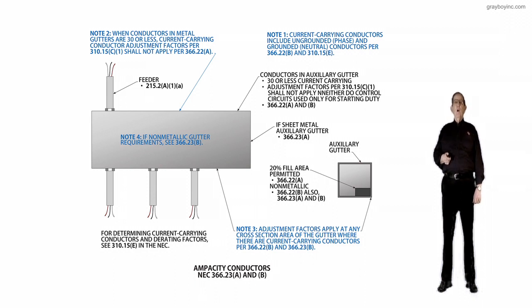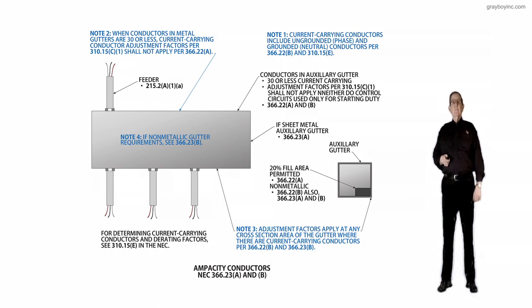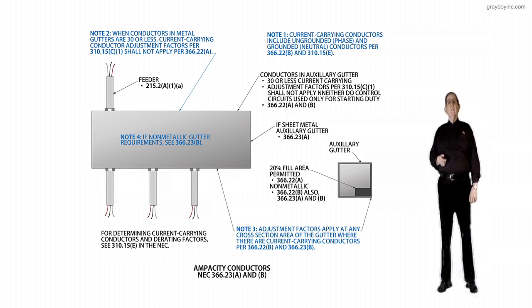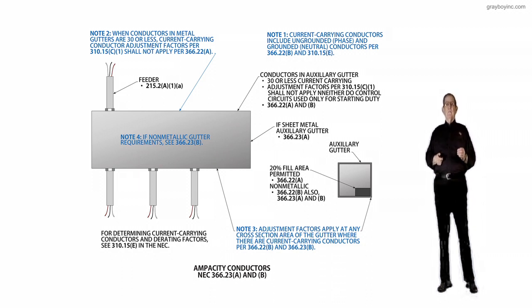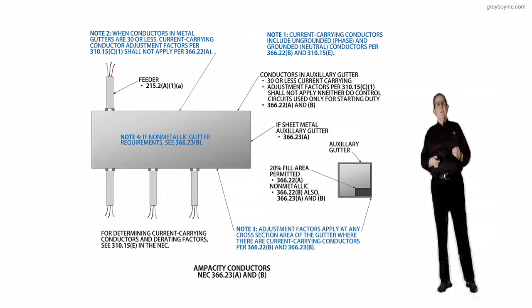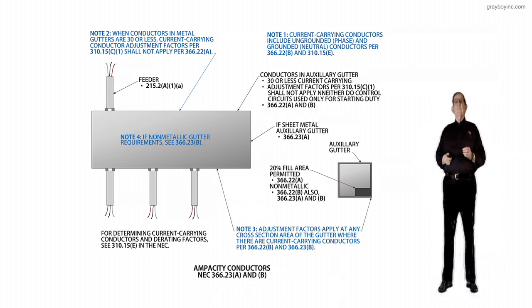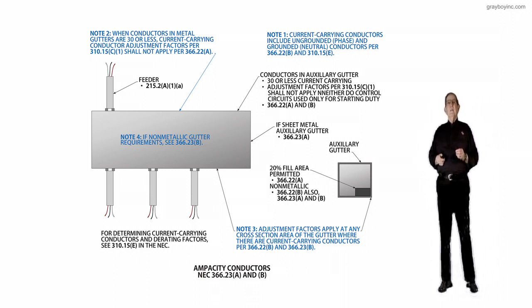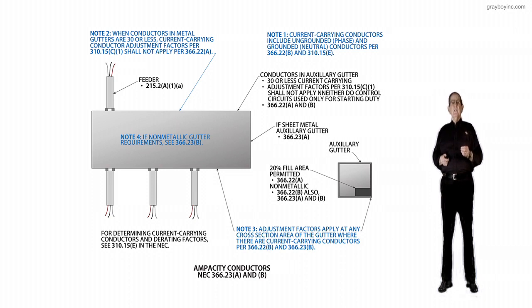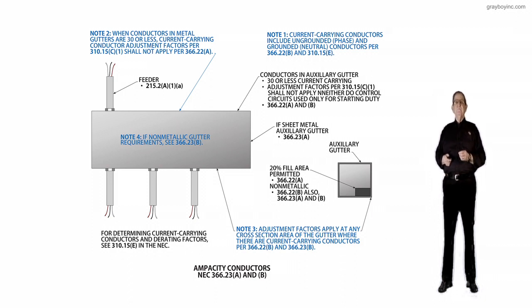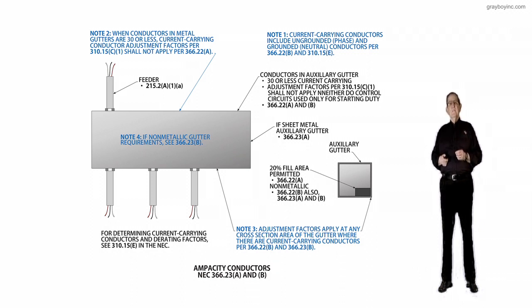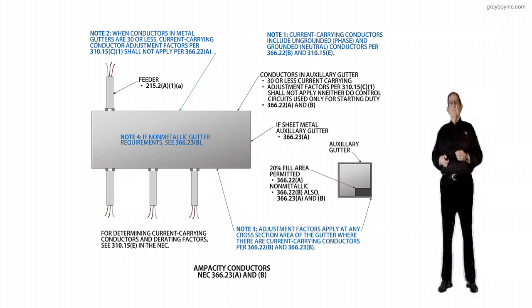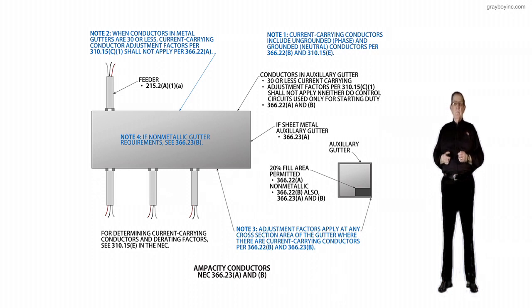Note 2 to the left of the illustration at the top of the auxiliary gutter says when conductors and metal gutter are 30 or less, the current carrying conductor adjustment factors that are required in 310.15C1 shall not apply for 366.22A. And then, of course, thirdly, we've already talked about it below it, so that would kind of wrap up this revision that has taken place.